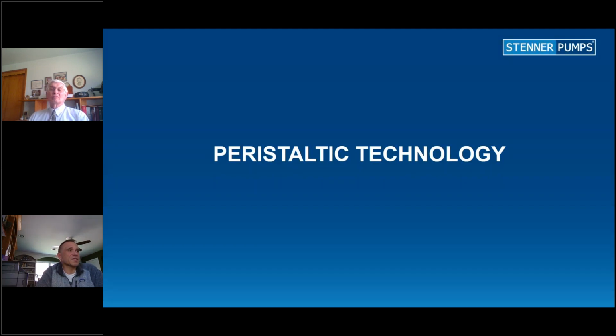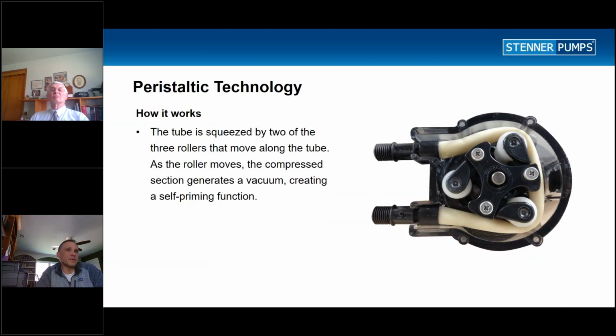So, peristaltic technology. The idea behind peristaltic technology is to be able to squeeze the tube to maintain suction and vacuum. And with that, we're always able to get 2 points of contact on the tube. So the rollers are always squeezing at least 2 points of the tube at all times to maintain prime and to prevent fluid from falling back.